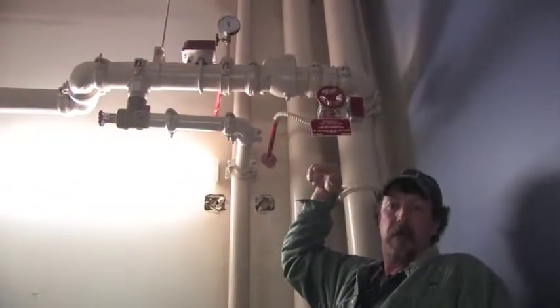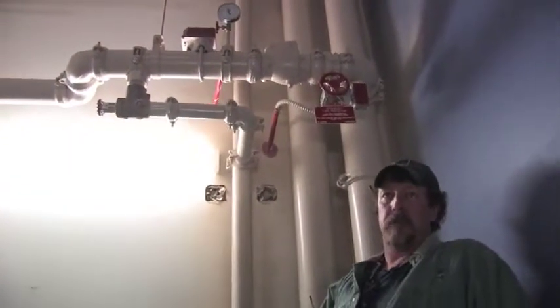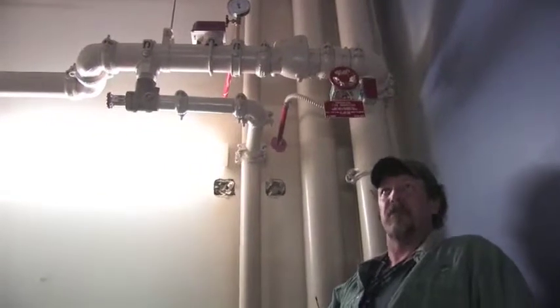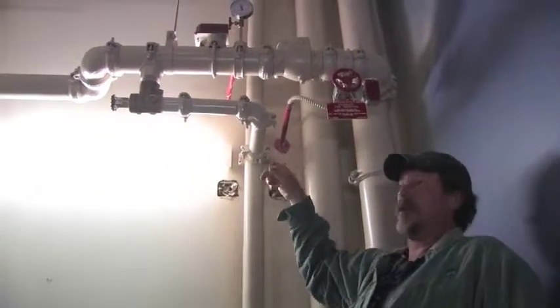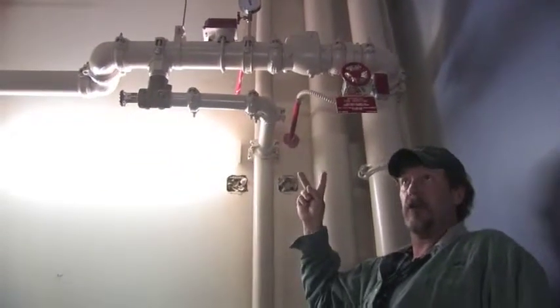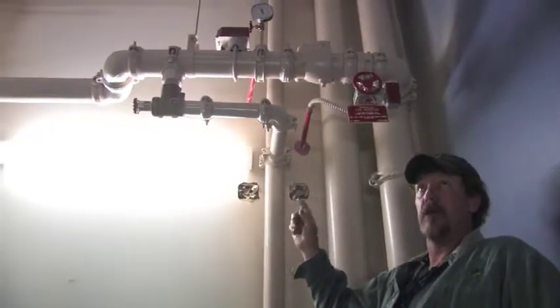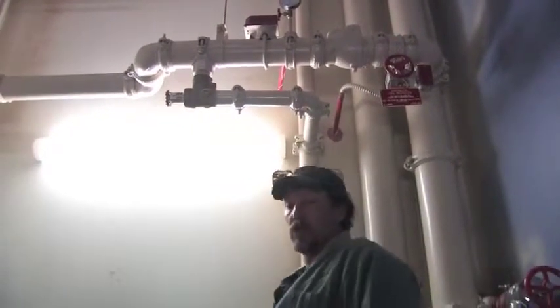Well, we can walk up to the second floor. I'll show you one of the pre-action systems and where the cabinet is. And second floor. This valve is doing the, what do they call it, basement floor, which is actually the first floor, but they're calling this the basement. And then, once again, there's 2 valves you have to shut to work on that system, and it's like that all the way up. There's 2 valves for everything.